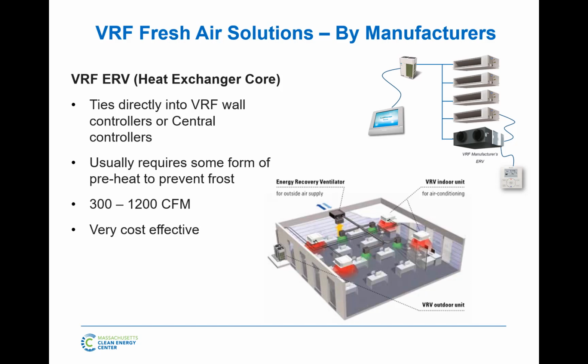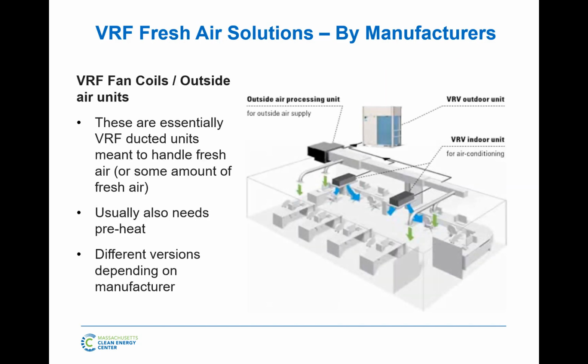If you do want to bring air directly into the space, I would look at different types of units, which we'll get into here, that can handle all heating and cooling of the fresh air. There are some fan coils you can use. So this one has refrigerant connected to it. You can use VRF fan coils that are designed to do fresh air. But when I say designed to do fresh air, what they really should say is it's designed to do fresh air in the south, not as much in the north.